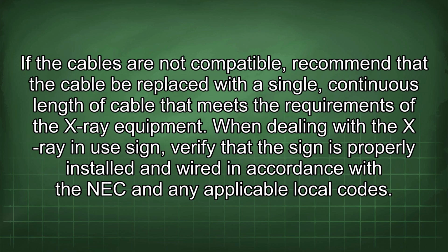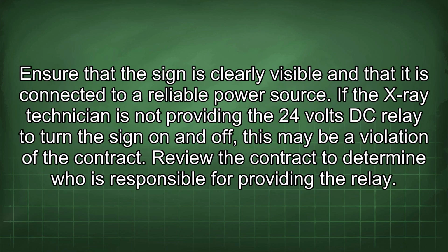When dealing with the X-ray in use sign, verify that the sign is properly installed and wired in accordance with the NEC and any applicable local codes. Ensure that the sign is clearly visible and that it is connected to a reliable power source. If the X-ray technician is not providing the 24 volts DC relay to turn the sign on and off, this may be a violation of the contract.